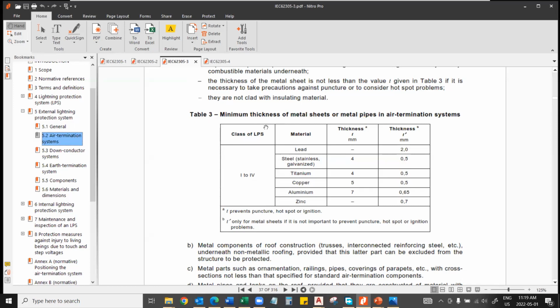So these are the design aspects, the key components you have to consider. If you have a roof and you need not to have a puncture, then you have to maintain this. But this is quite impracticable when you have metal sheets, because you now have metal cladded sheets with these wafered roofing solutions. But if puncturing is allowed, you go with these thicknesses, only for metal sheets, if it is not important to prevent puncture, hotspot, or ignition problems. Depending on the items being stored inside the facility, you can go with this as well, but you have to consider other aspects of the LPS with that. So, going back to the slide.